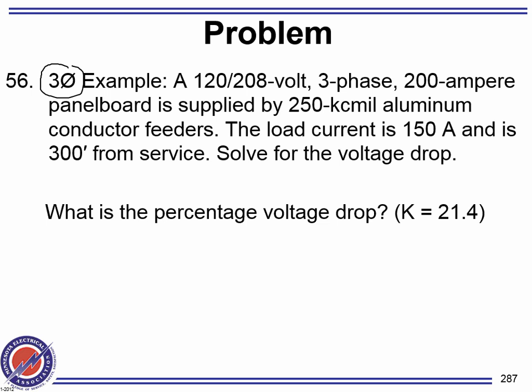When you do the voltage drop, which voltage would you use? The 120 or the 208? Always the highest voltage for three phase. Phase to phase. 208.